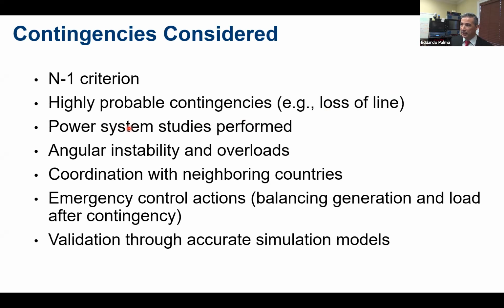hardware in the loop testing, meaning that we inject these types of conditions that we consider the most important ones, and we verify the outcome in a loopback mode through feedback. And the feedback coming from measuring the time of the control actions gives us 100% guarantee that when it happens on the real system, our models look exactly the same as what is going to happen in Georgia. So we do model these systems. We not only include power system studies. Angular instability and overloads happen, so they had to be compensated.